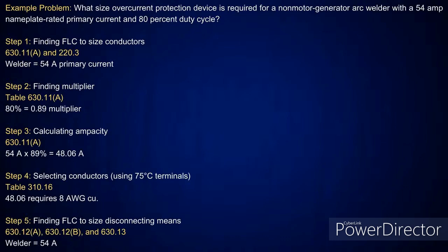Now I'm going to look at the conductors, because I'm doing the conductors and then I'm going to do the overcurrent device. And if you look at the overcurrent device, just to get people in the right direction to start off, I pick up 630.12A. It tells you should have an overcurrent device rated or set, and listen to what it says one more time, at not more than 200%. So that, once again, you can't exceed it because it says not more. So here's another high percentage where we're doing what? Dropping down to the next standard size. So I'm going to size the conductor, which is a number 8 conductor. I go over, look at Table 310.16, and I pick that up for the 75 degrees C column. The next size above 48.06 amps is 50 amps, which is number 8 conductor.